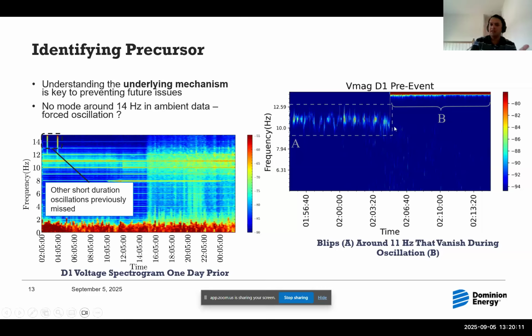In this event, if you look at the spectrogram of voltage magnitude at the data center bus, there are these blips labeled as A, bursts of energy happening again and again around 10 to 11 hertz. As soon as the oscillation starts, which is period B, these vanish. So do they have a relationship with each other?